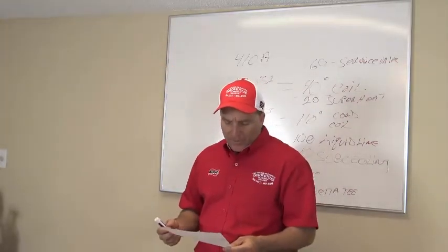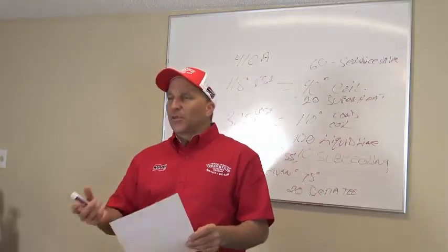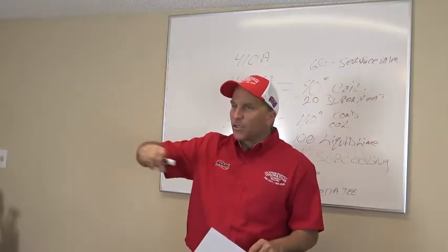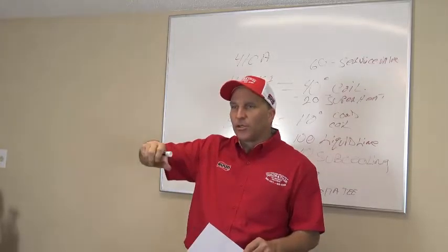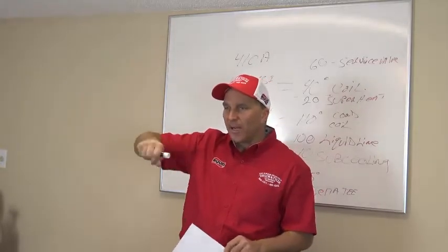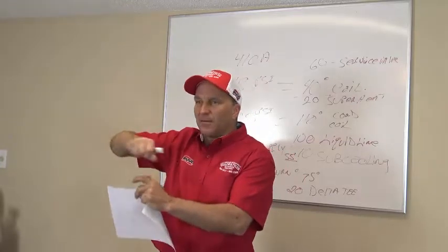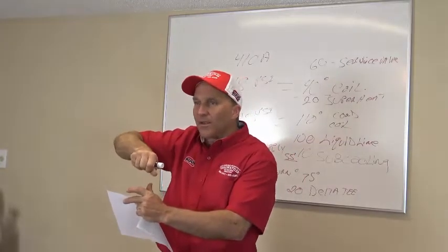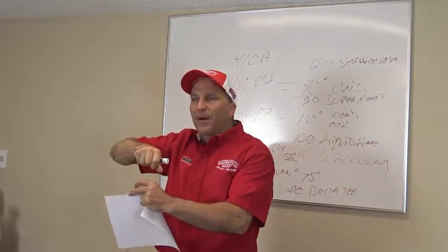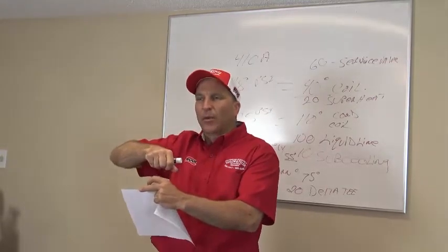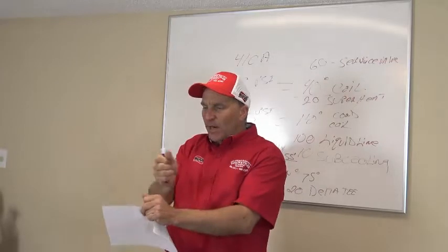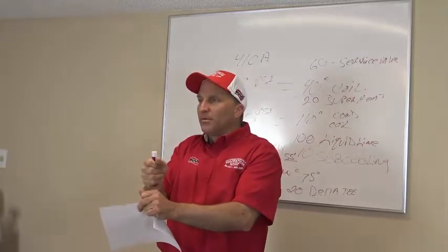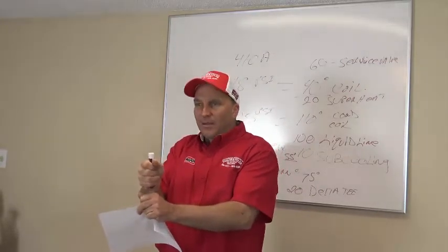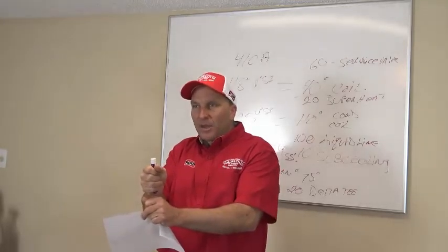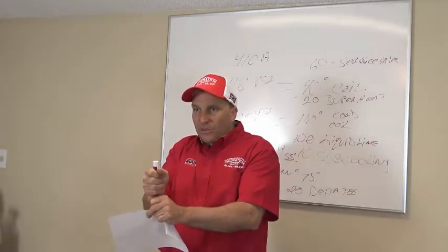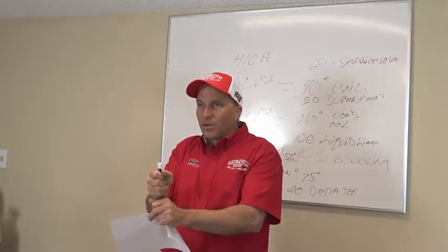If it's loose, you can actually turn that fan motor over and shake the motor. What I mean by shake the motor is you can grab the fan blade and shake the shaft of it, and it'll go back and forth. If it shakes, that's a loose bearing up inside of that thing, because grab a brand new fan motor out of the box and try to move that shaft. It won't move. But grab an old one and shake it, the bearings are going bad in that motor. Okay? That's no bull. You're telling them straight out that the bearings are loose, and you can shake it and show it.